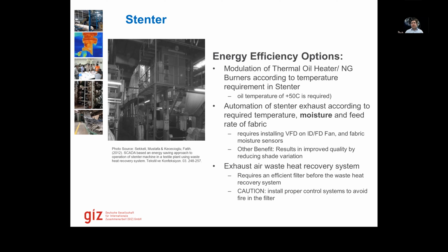When we go to the oil heater, the outlet temperature is 300 degrees Celsius, and the oil returning from the stenters is coming at 295 to 296 degrees Celsius. So only a 3, 4, or 5 degree delta T is gained inside the stenters in this case.